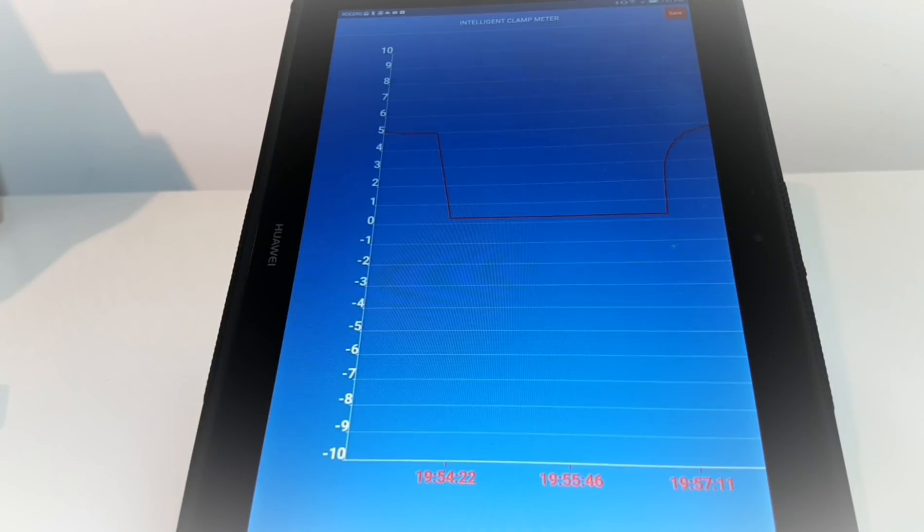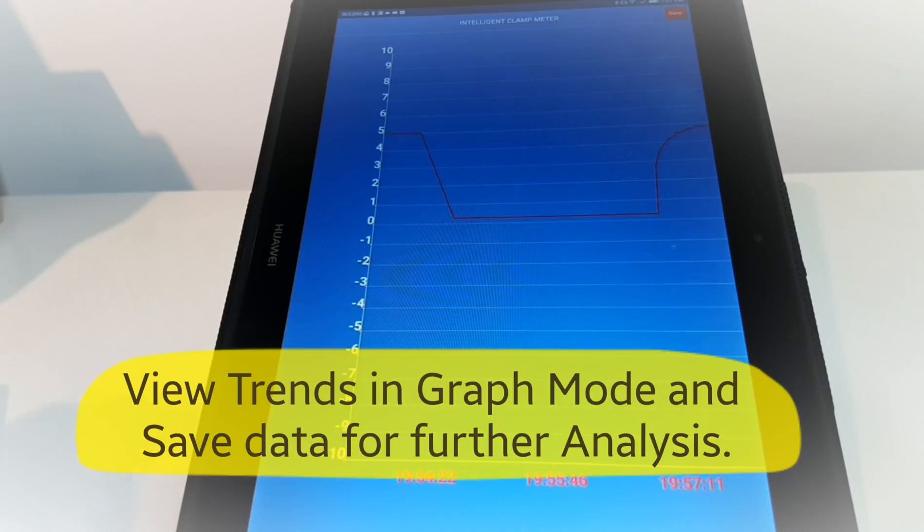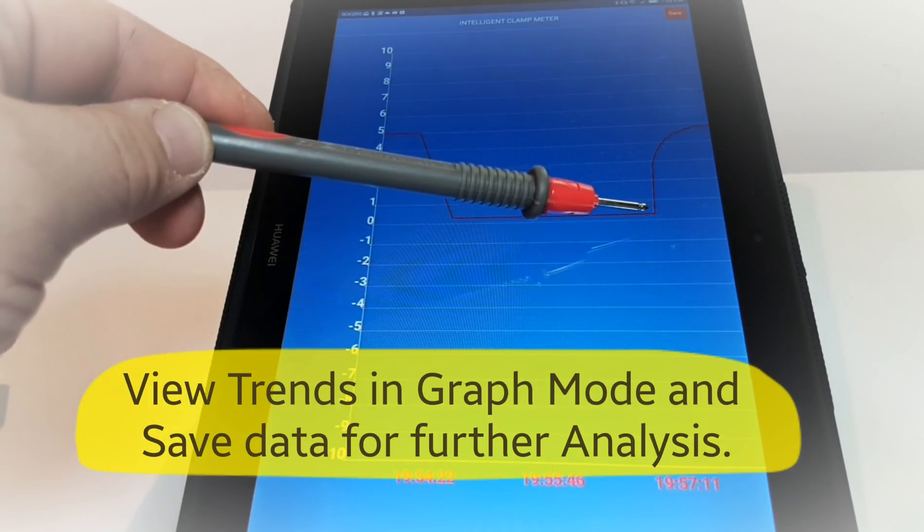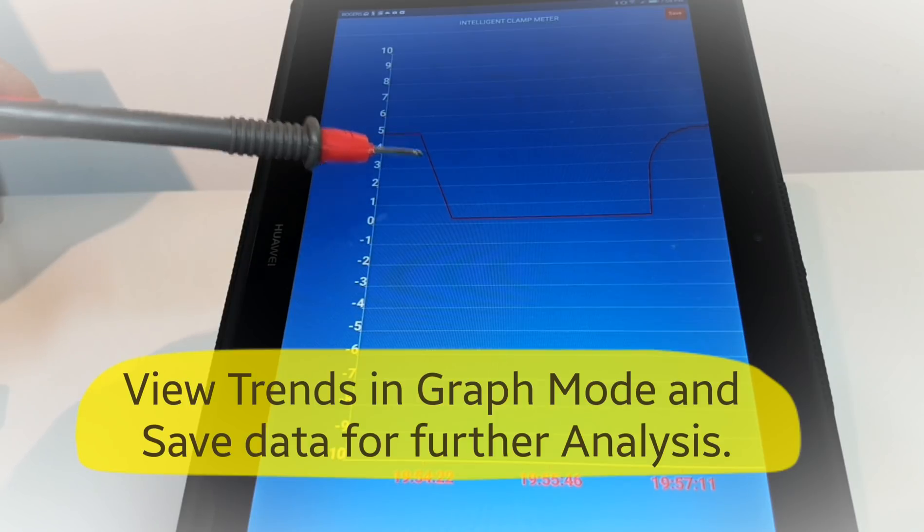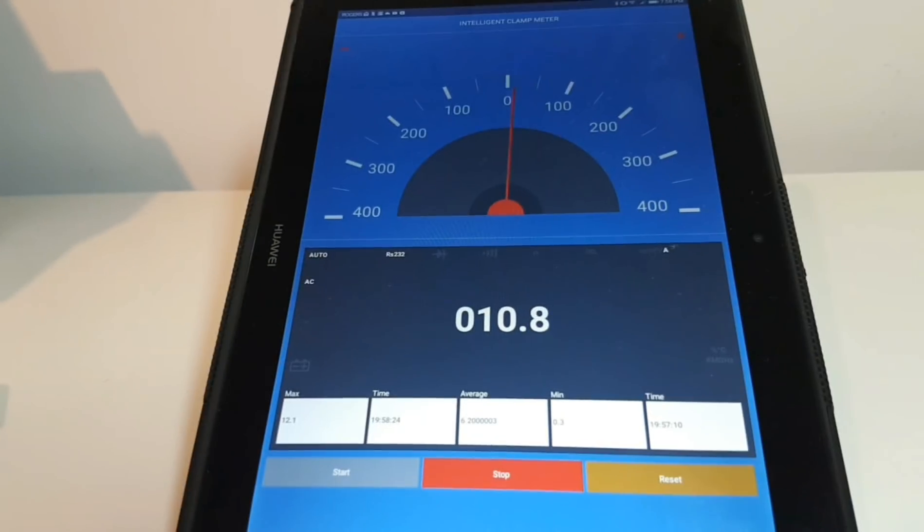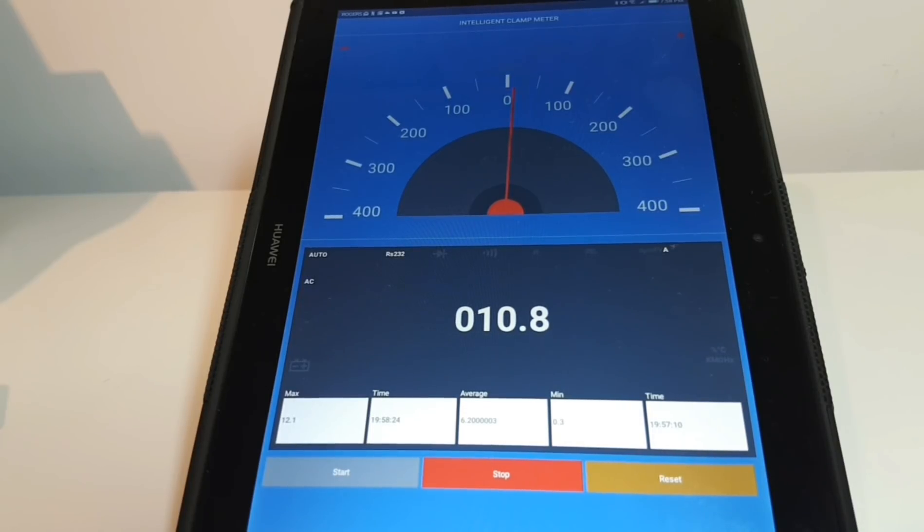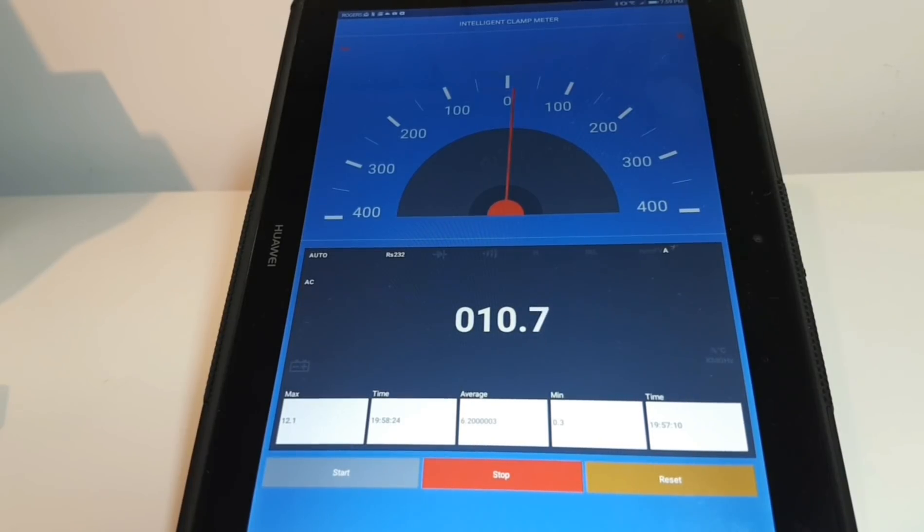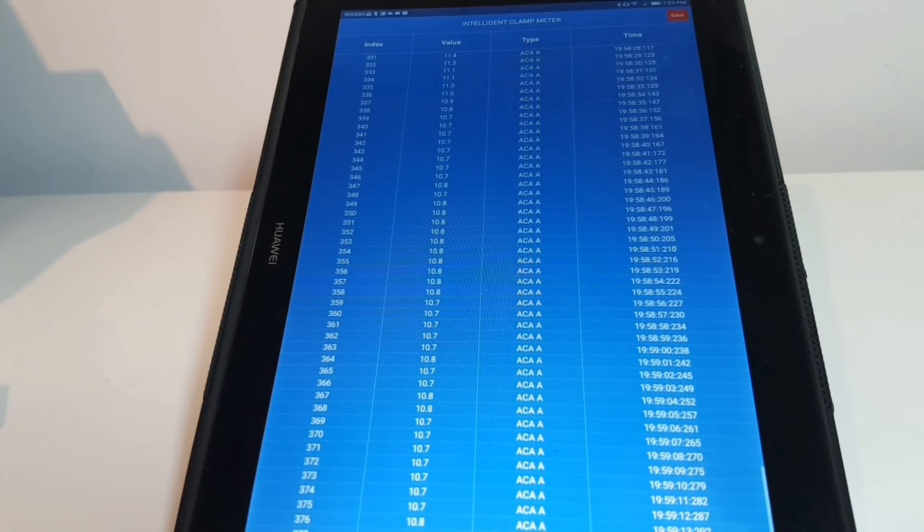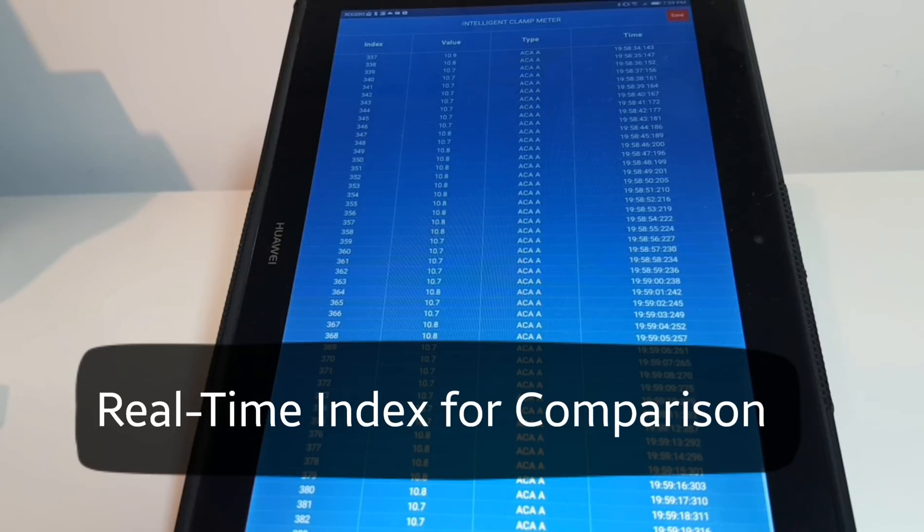And the graph mode is really nice because it gives you a visual approach to data logging as well. So here now is when we were basically flatline when the unit was turned off, the unit was on here, off and then turned back on. Now we're in high power and you can see we're pulling in twice the amps again, pushing 11 amps right now, showing up as 10.7. So the nice thing about the software is the fact that it really is very simple to operate and you do have this sort of data logging feature. This is another one where it's giving you an index of all of the values with a timeline. Can come in very handy once again.